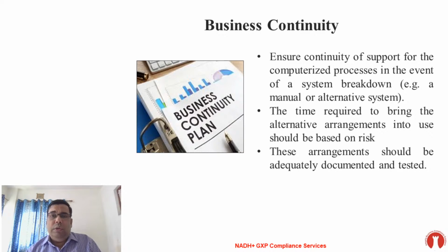Just before the FDA inspection, some 1 month before, there was a fire in the QC instruments, and a lot of HPLCs were burnt, and a lot of data was burnt. But thank God we had the disaster recovery plan, DRP, because it is a part of the business continuity plan. On that basis, we had proved that if a disaster happens, we will lose only 8 hours of data.